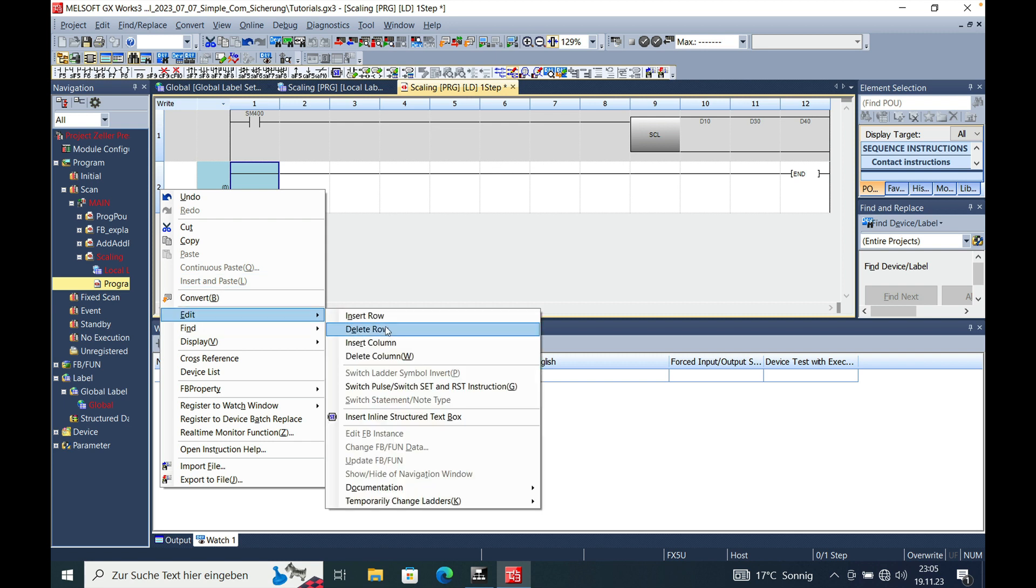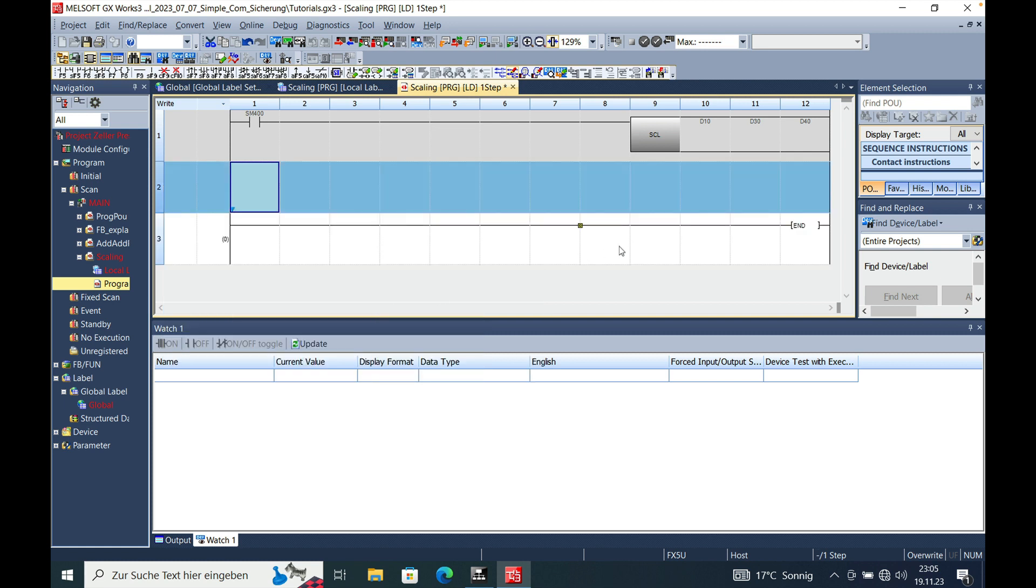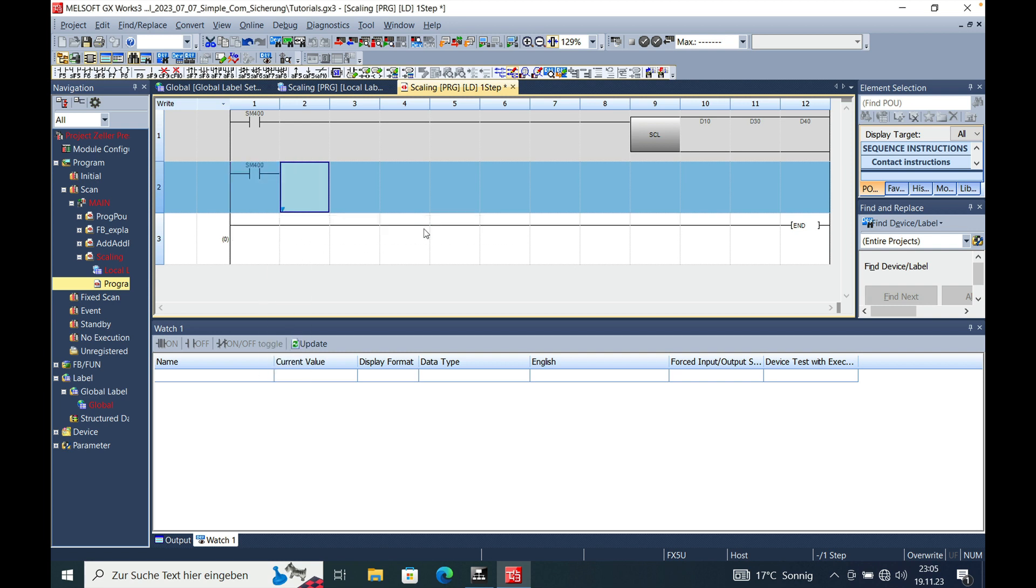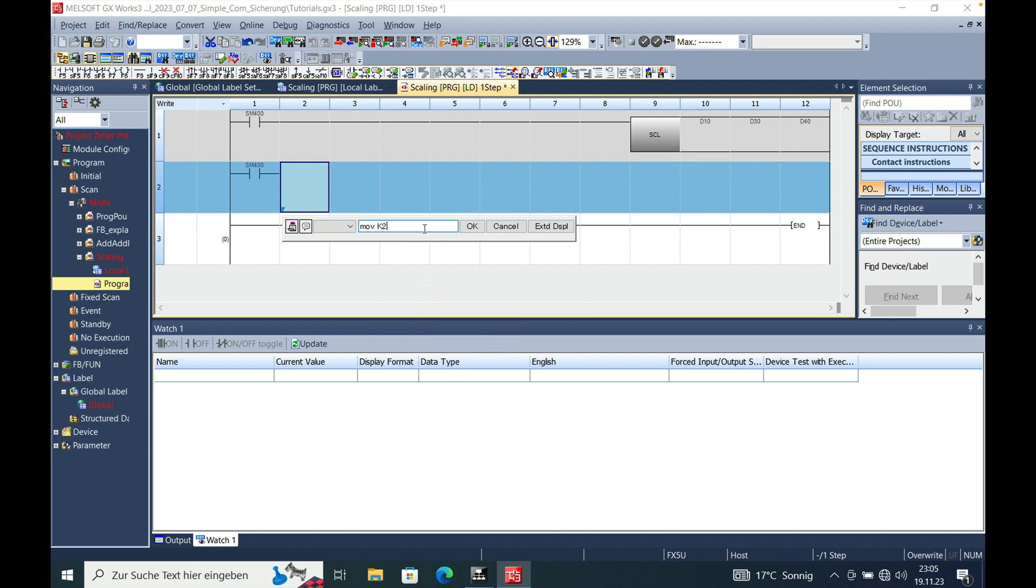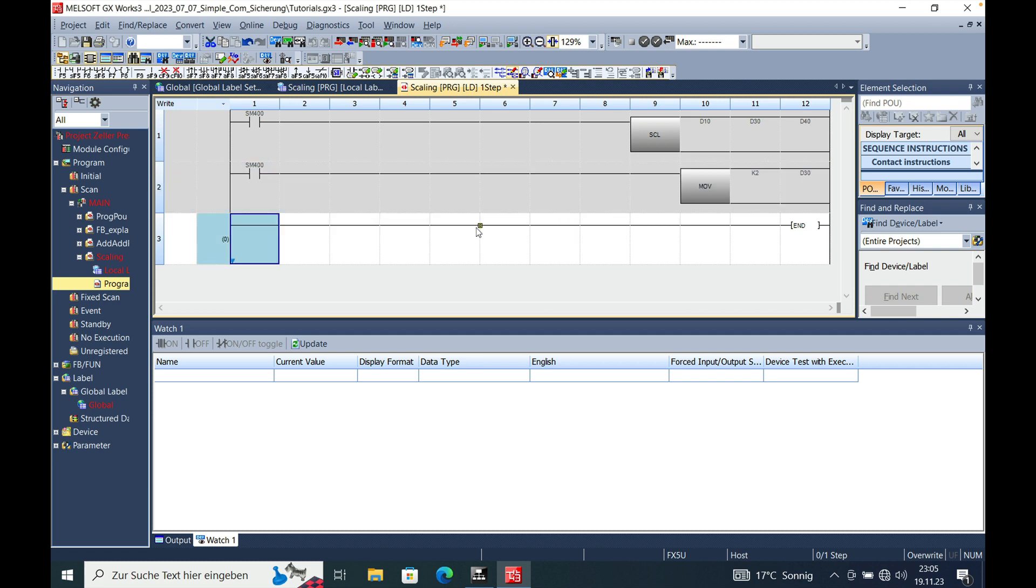And then we need to make an initialization of the scaling function itself. There we go. Put a normally open in front of it again and call it also SM400. And then you make a move instruction. Move K2 to the D30 which describes the length of your scaling function. And this way your scaling function is initialized.